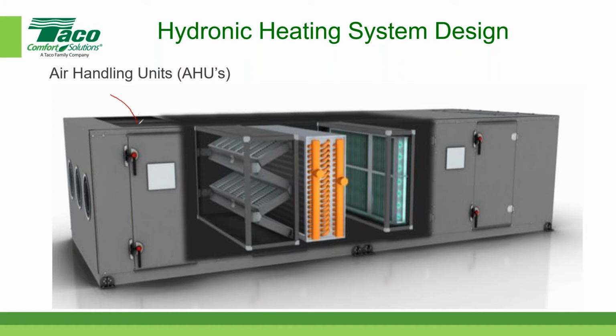In this section here, this is where you would connect the ducts, either through the back, as this could be the outside air, this could be the return air. Let's say I'll label this return air, this could be the outside air. And then the air goes and passes through a series of filters and then through these hydronic heating coils. And that's where our piping system, again, and you're going to see this in more detail in a minute. So we might have a supply pipe that goes in this, fluids flowing in this direction, and a return pipe, fluid flowing in this direction.